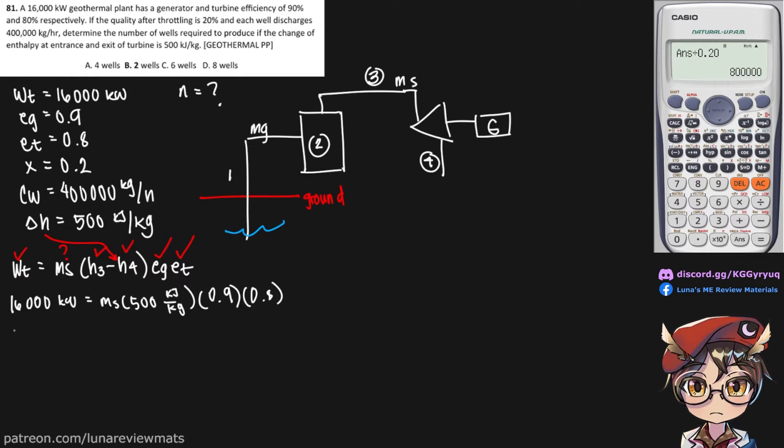And this should give us 44.4 kilograms of steam per second. Now notice we are working on a kilogram per hour basis, so if we multiply this by 3600, we will arrive at a value of 160,000 kilograms of steam per hour. But we can't really use this yet because we need to find mg.